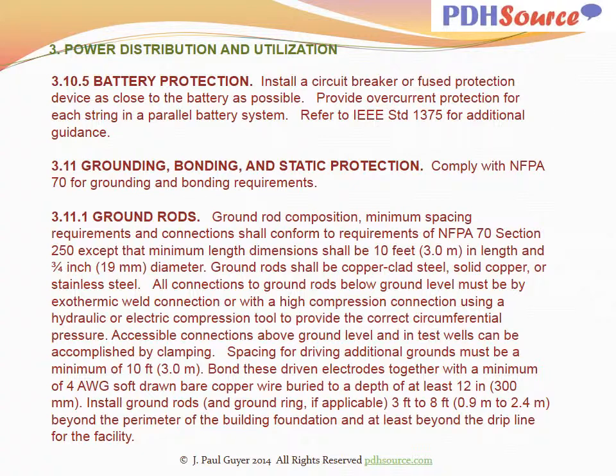Accessible connections above ground level and in test wells can be accomplished by clamping. Spacing for driving additional grounds must be a minimum of 10 feet. Bond these driven electrodes together with a minimum of 4 AWG soft drawn bare copper wire buried to a depth of at least 12 inches. Install ground rods and ground ring if applicable, 3 feet to 8 feet beyond the perimeter of the building foundation and at least beyond the drip line for the facility.